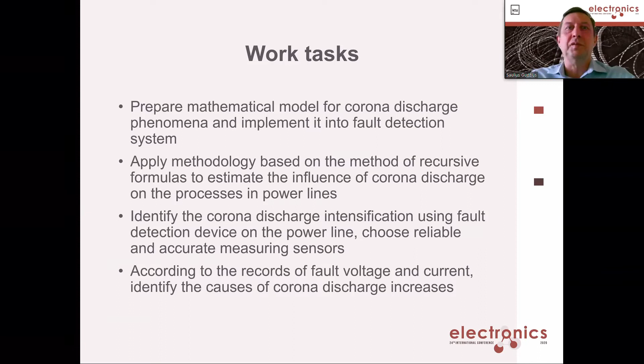Corona is a naturally existing phenomenon on power lines, and it exists all the time if we increase the voltage higher than its critical corona voltage. You can hear corona during rain if you are not so far from the power line, or during icing, when power lines are iced and you can see and hear some noise. This means corona exists in this power line, and it's a natural situation.